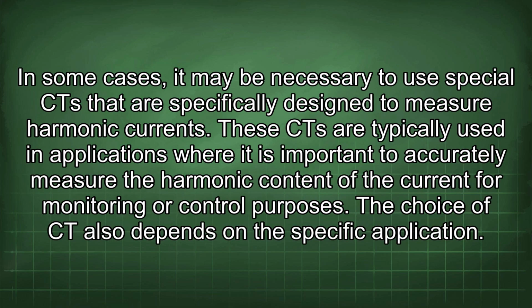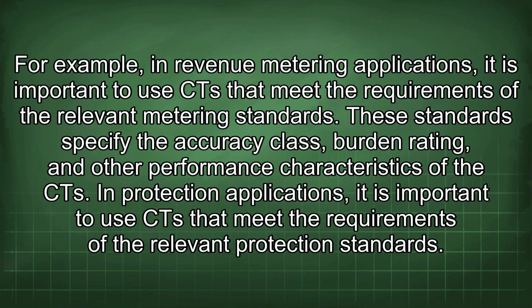In some cases, it may be necessary to use special CT that are specifically designed to measure harmonic currents. These CT are typically used in applications where it is important to accurately measure the harmonic content of the current for monitoring or control purposes. The choice of CT also depends on the specific application. For example, in revenue metering applications, it is important to use CT that meet the requirements of the relevant metering standards. These standards specify the accuracy class, burden rating, and other performance characteristics of the CT.